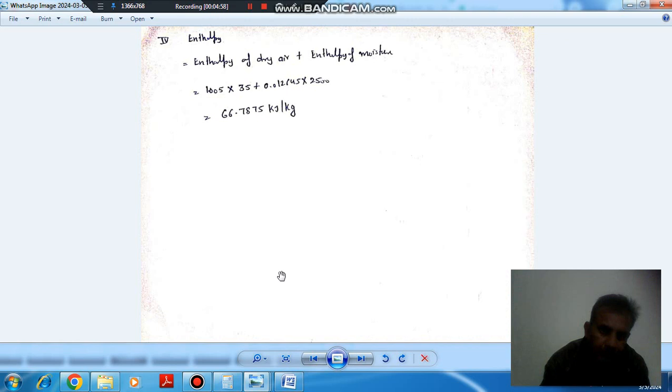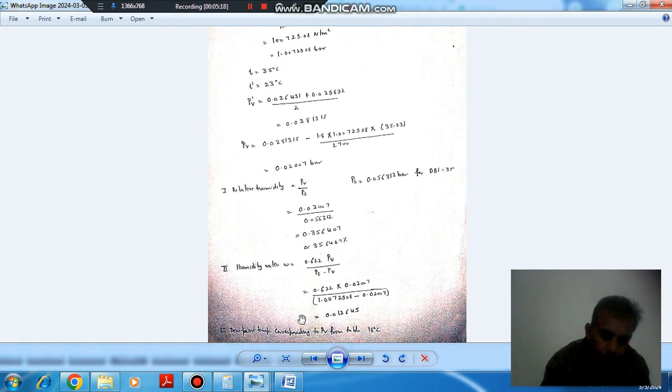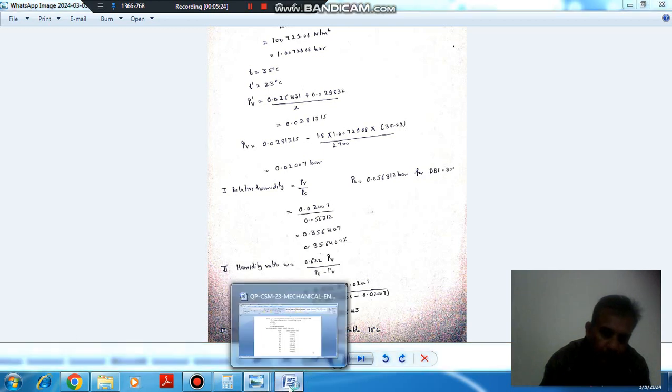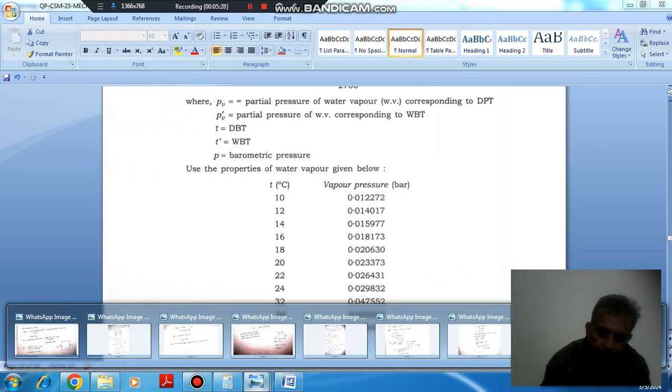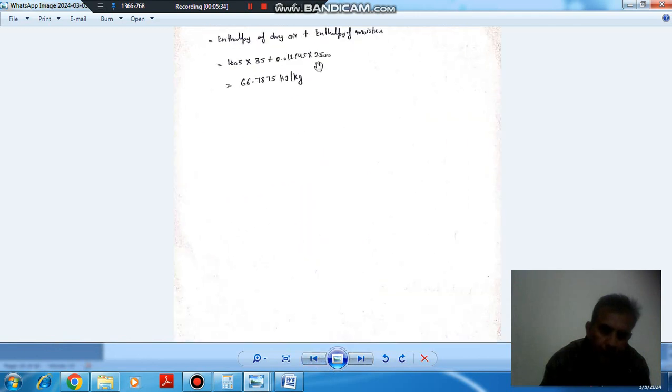Now enthalpy. Enthalpy consists of enthalpy of dry air plus enthalpy of moisture. DBT is 35 degrees, C_P is 1.005. This is enthalpy of dry air. And moisture content we have just calculated, humidity ratio is 0.01645. This is the moisture content in 1 kilogram of air, multiplied by enthalpy which is 2500. It will be 66.7875 kilojoule per kilogram. Thank you.